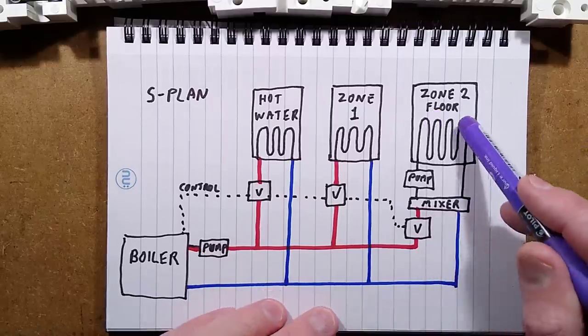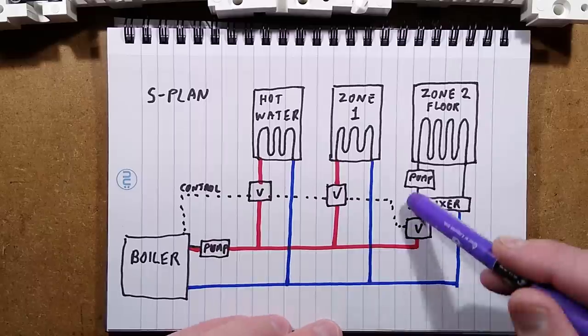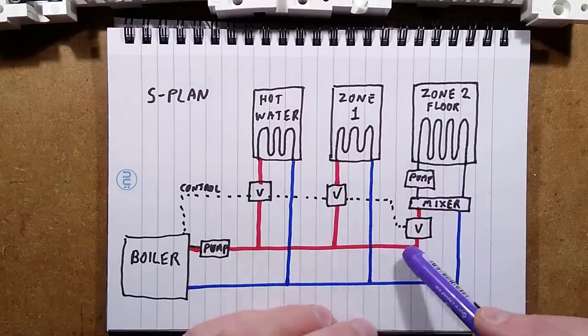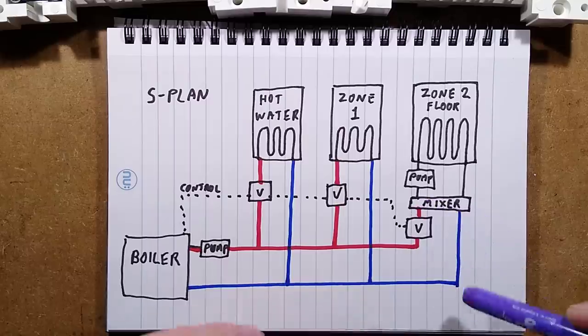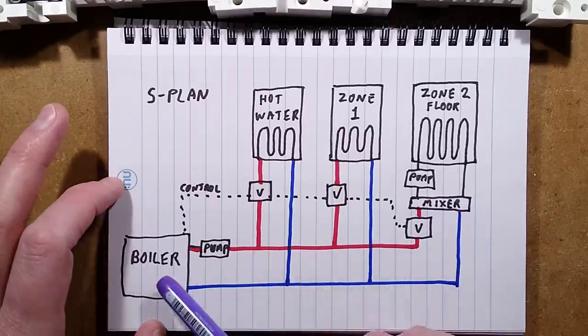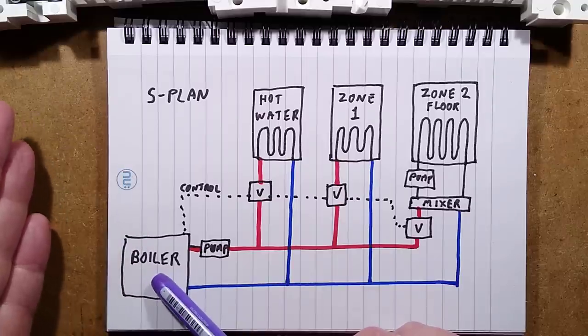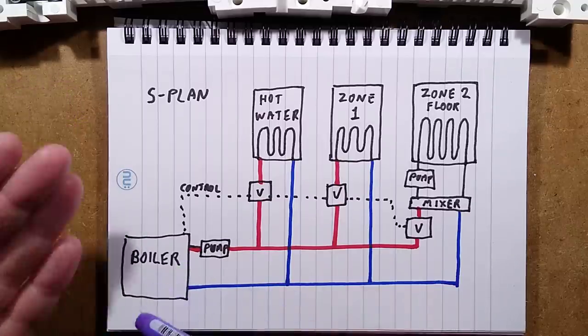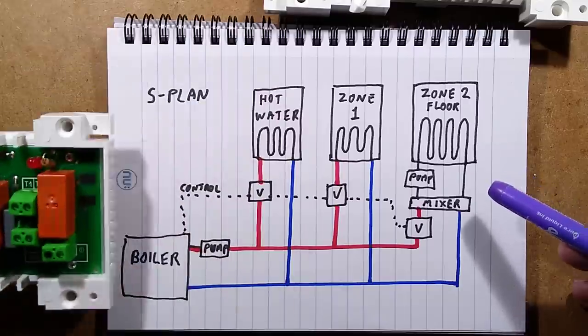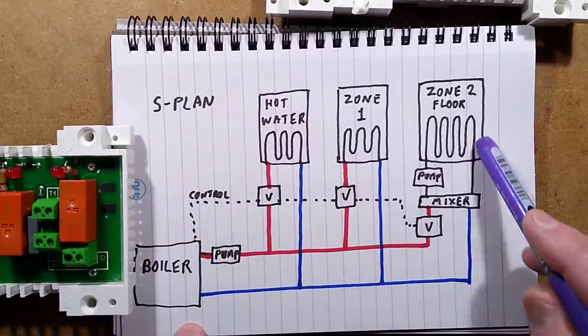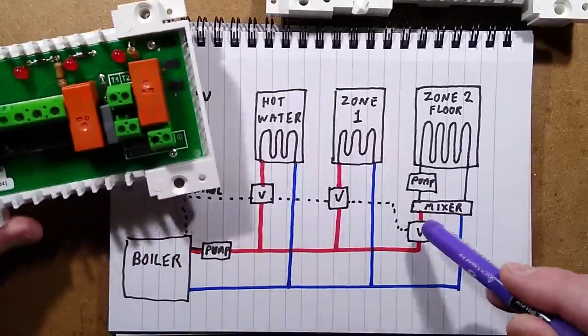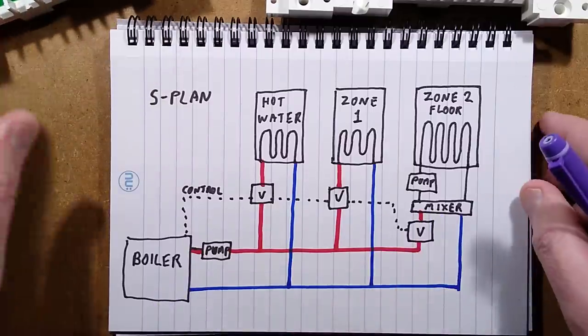The difference with underfloor heating is they don't just run water straight through the underfloor heating hose. It's actually continually circulated by its own pump, and there's a mixer to regulate the temperature, so it only pulls in hot water as needed. The boiler isn't too bothered about that because it's still passing water through the system — once it reaches its set temperature it will still be pumping water but just go into standby until more heat is called for. The point of these units is that they control everything for the underfloor heating: the pump, the valve, and the wiring facilitates sending that signal back to the boiler.